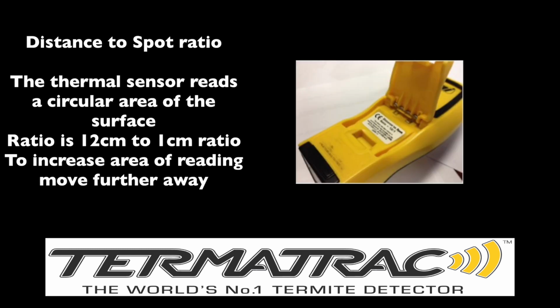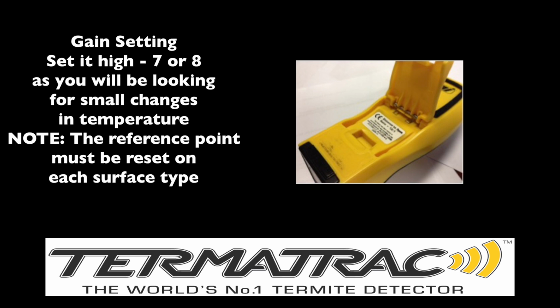The distance to spot ratio. The thermal sensor reads a circular area of the surface. A ratio is 12 cm to 1 cm, and to increase the area of reading, move further away. Set the gain setting to high, either 7 or 8, as you'll be looking for small changes in temperature. Note, the reference point must be changed for different surface types.